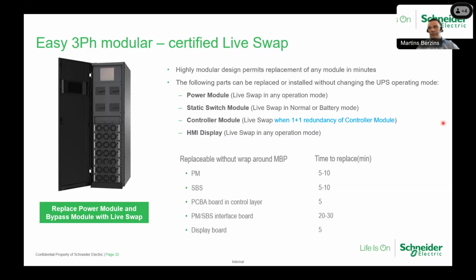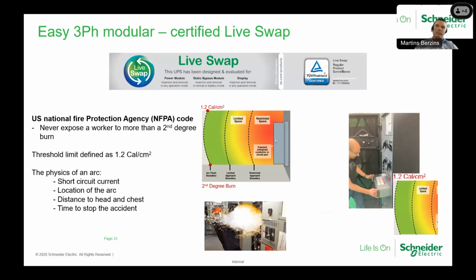In the market, in other UPSs, we know that there is a so-called hot swap feature, which is named similarly, but let me explain the difference, why this is not a hot swap. This is a live swap feature. So what does live swap actually mean? It means that when the operator or worker is replacing the power module, and there is an accident, even if it's a small chance of happening, an arc flash, the arc flash is limited to 1.2 calories per square centimeter, according to the US National Fire Protection Agency code. So basically this is a threshold for a safe environment for the workers. Never expose a worker to more than a second degree burn.